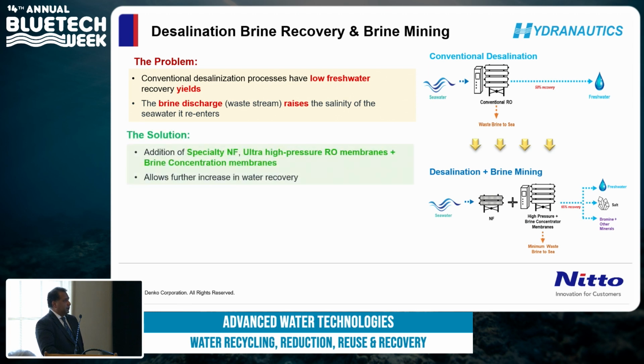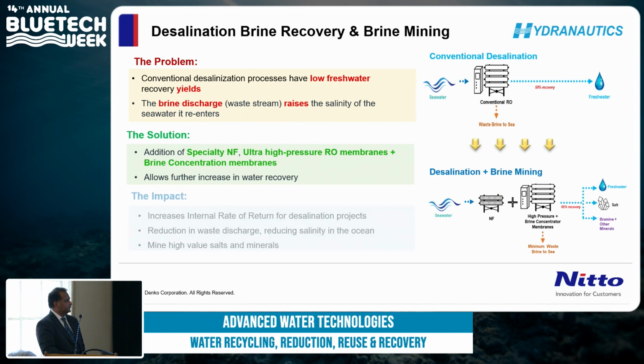And as I spoke of, there are new innovations in terms of specialty NF, ultra-high pressure RO membranes, and what we like to call the brine concentration membrane, because this takes care of your highest solids, which are to the tune of 12%, and takes it to 22%, and can help you with the 3 water sources that we spoke of. And it also allows a further increase in water recovery, so you can reach a higher recovery of 65 to 70%.